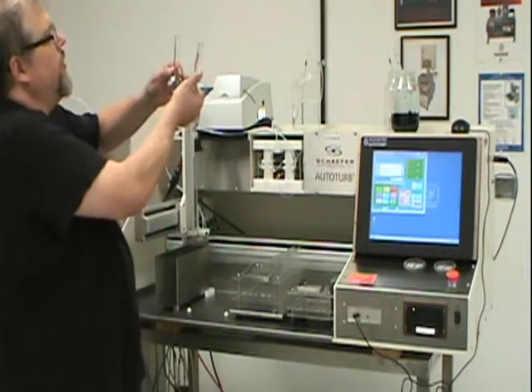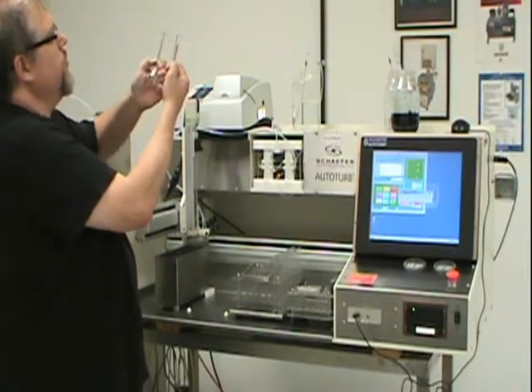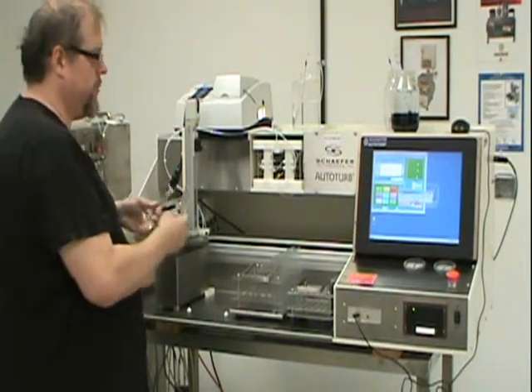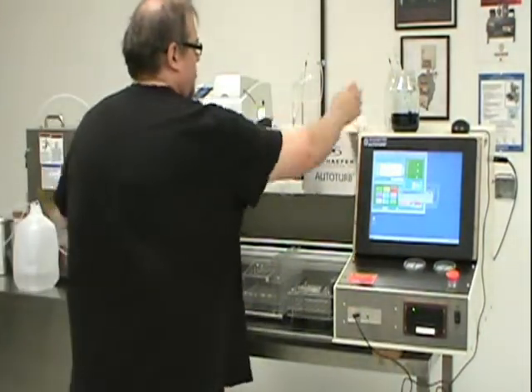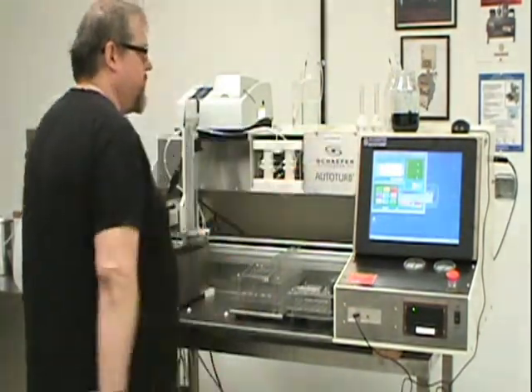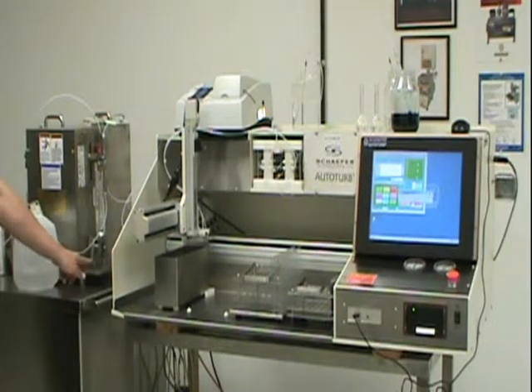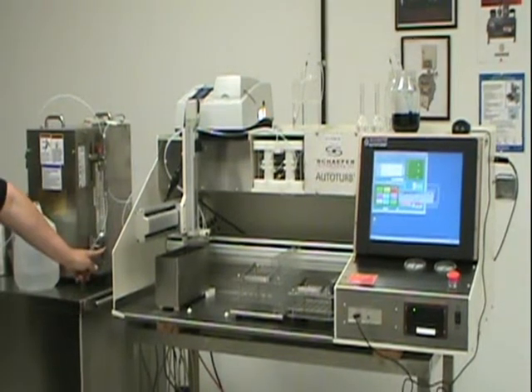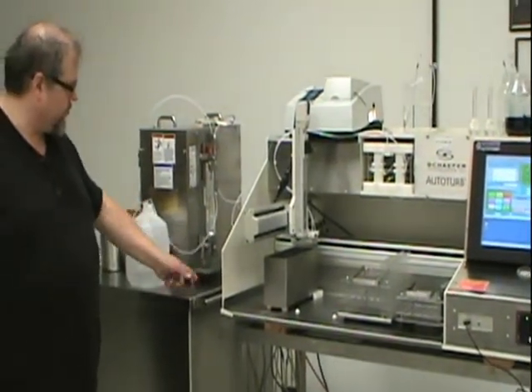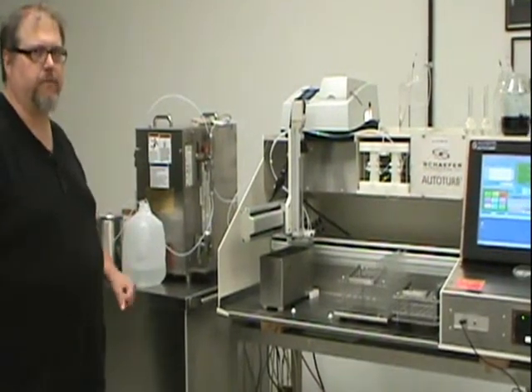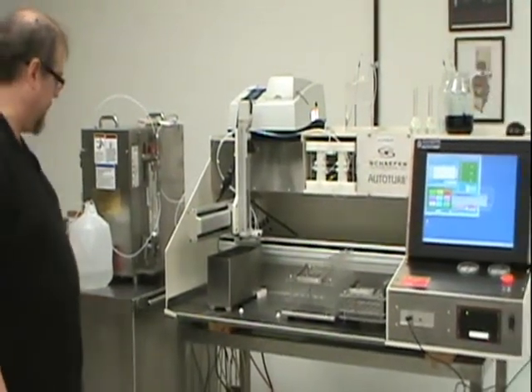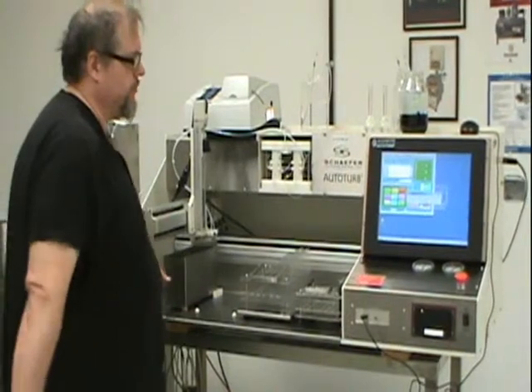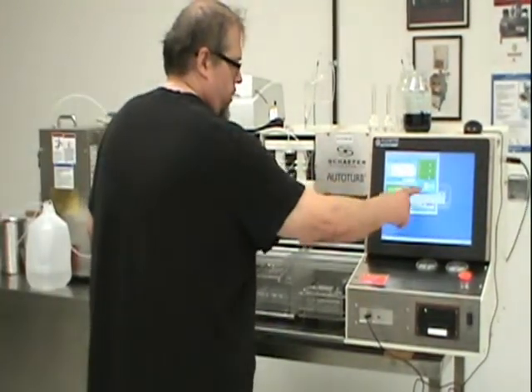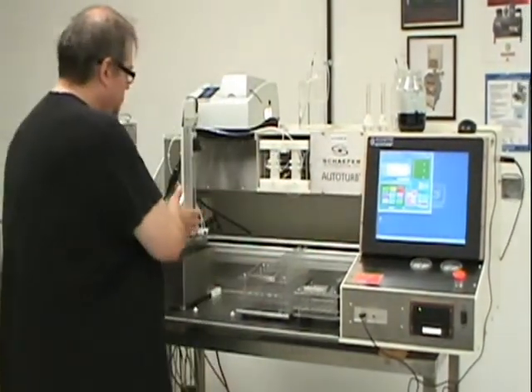Once it's done, we check the volumes. We want to make sure that we're on the lines, which we are. Because this machine has been set up recently. If not, we would have to loosen this nut here and then adjust the screw to either increase or decrease the flow of fluid. And then have to retest over again. Once we're done, we press OK. We send the arm back home.